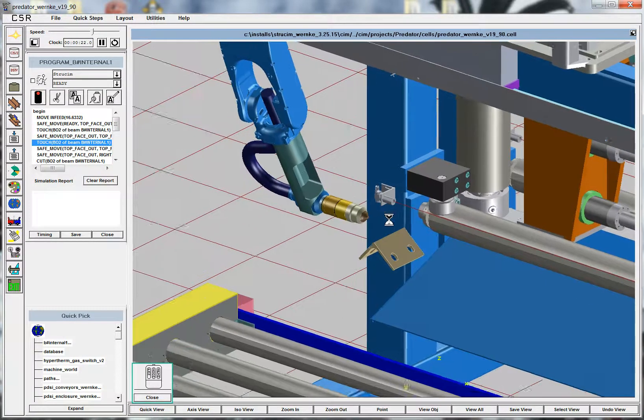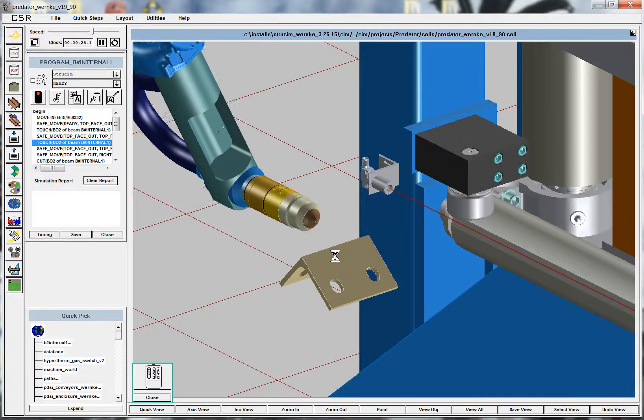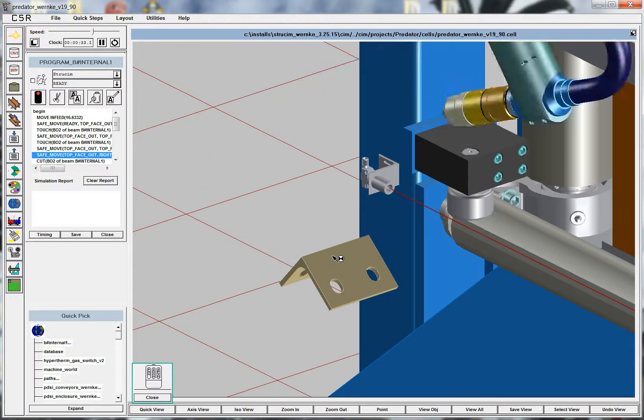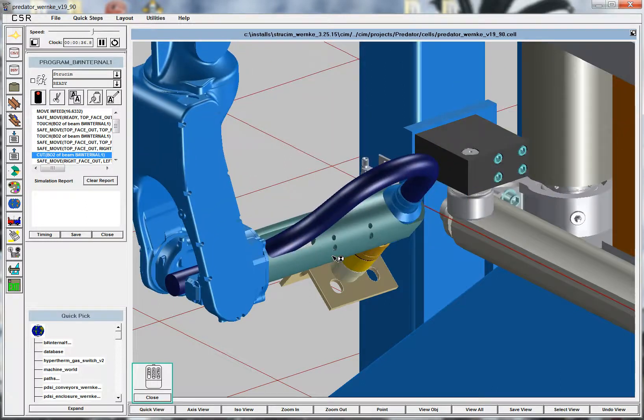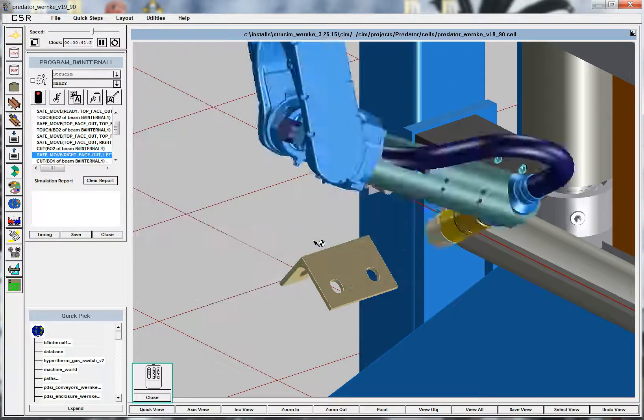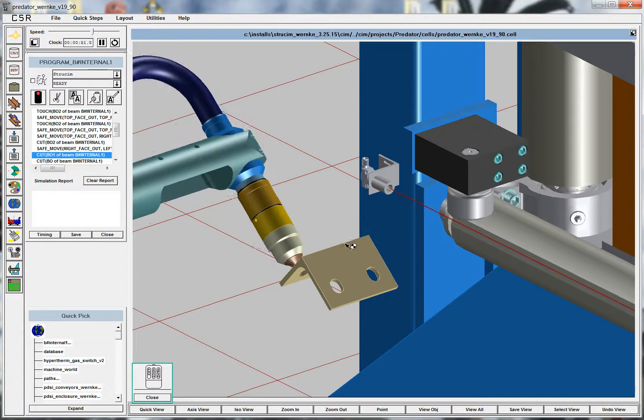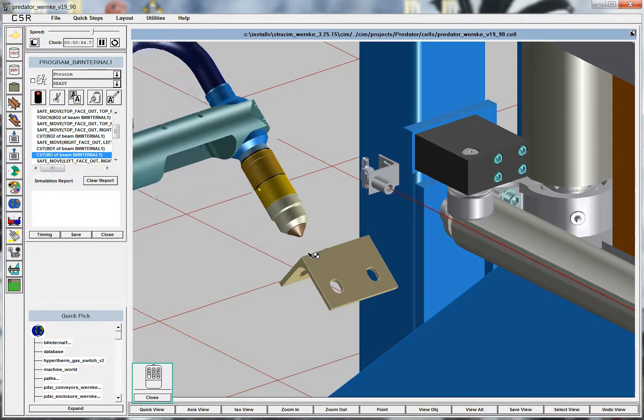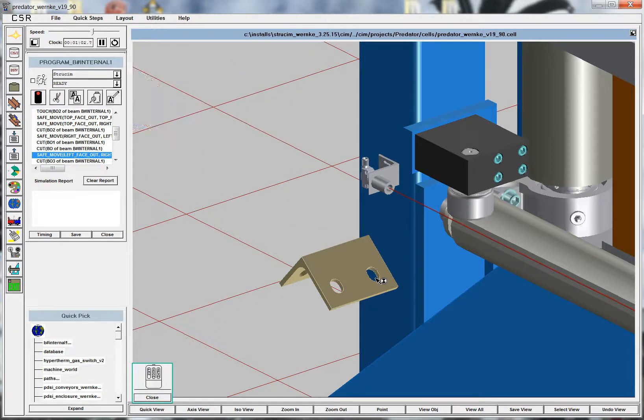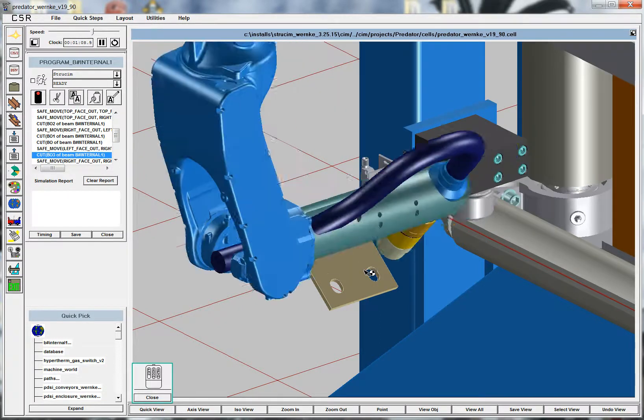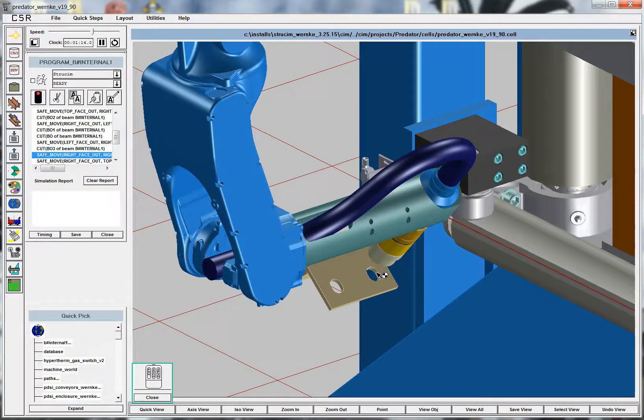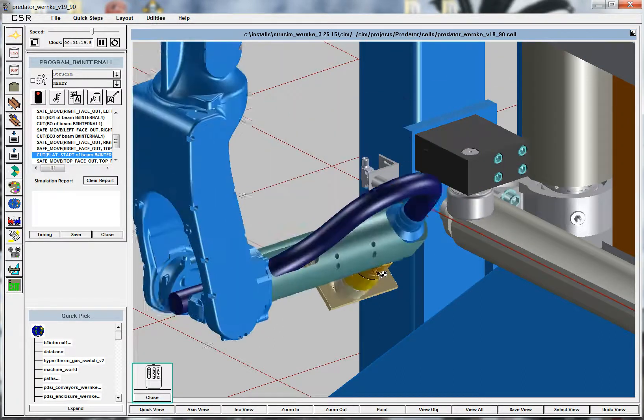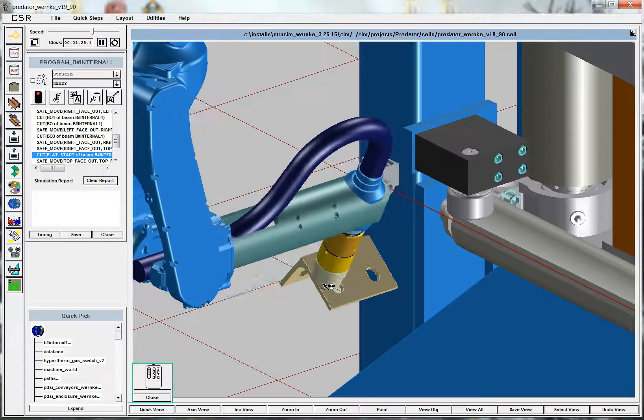We use a Hypertherm torch, and we have it connected electrically to a touch system, so that you can see that it touched, and it could find the actual positions of these holes, positions of this full clip angle. So that when we go and we cut, we compensate for it. It's a few millimeters off, and we still provide the accuracy required to cut the clip angle.